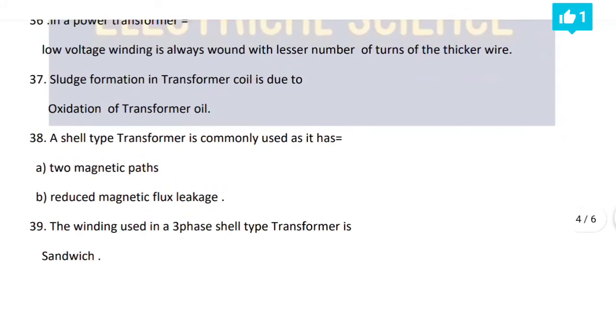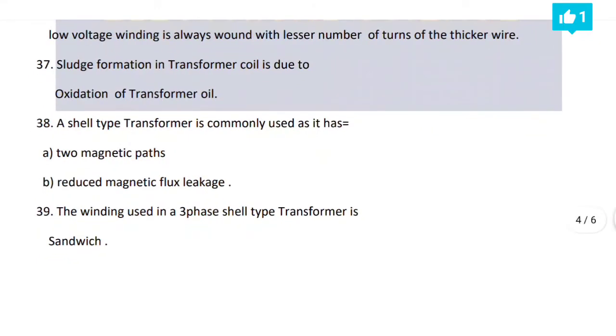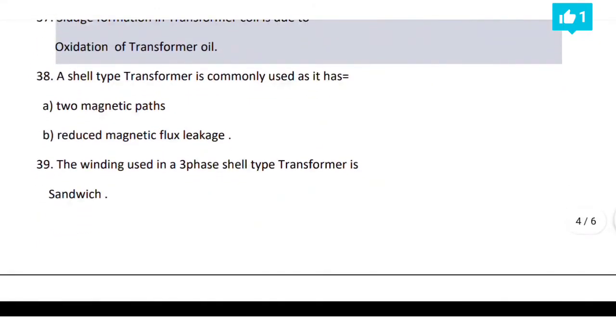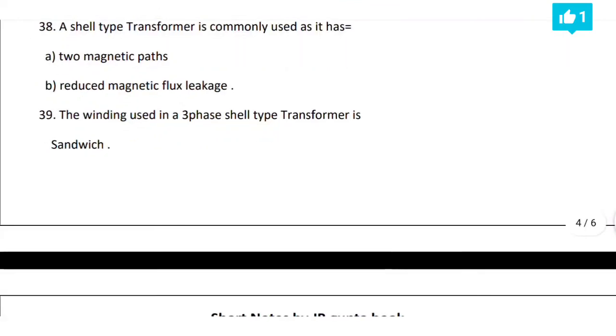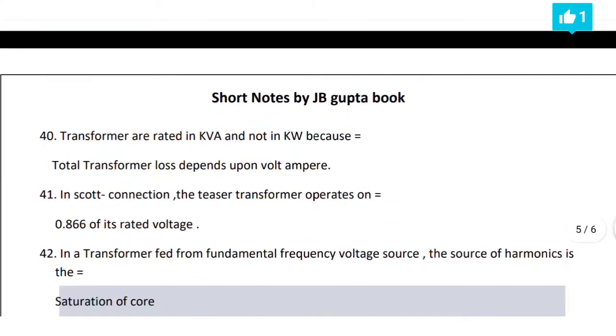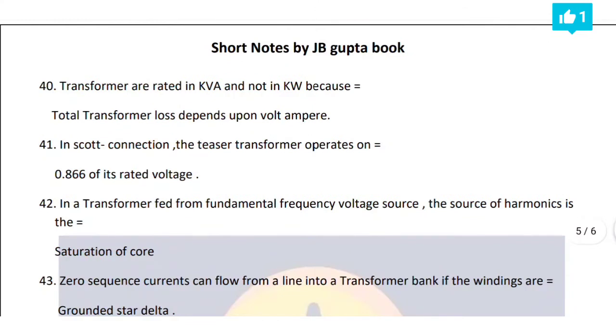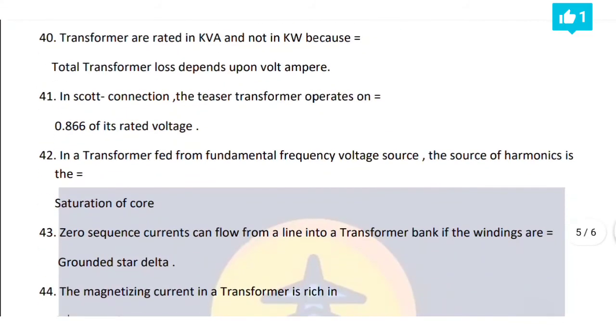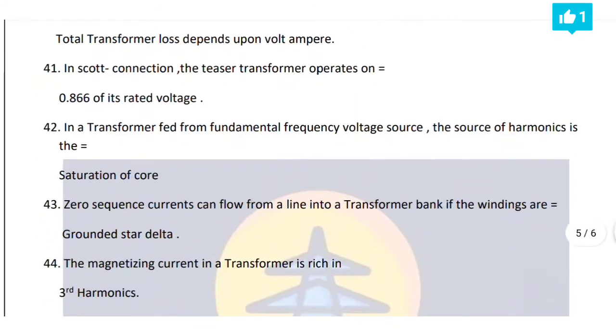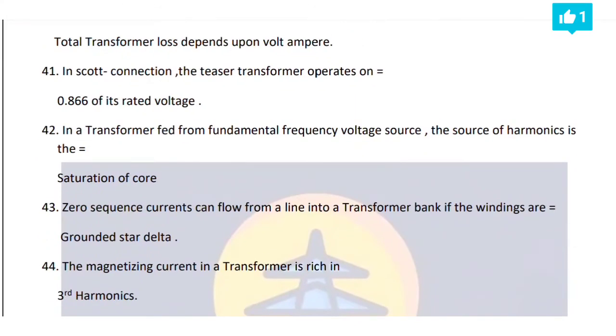38th point, a shell type transformer is commonly used as it has, first point, two magnetic paths, second point, reduced magnetic flux leakage. 39th point, the winding used in a three-phase shell type transformer is sandwich. 40th point, transformers are rated in kVA and not in kilowatt because total transformer loss depends upon volt ampere. 41st point, in Scott connection, the teaser transformer operates on 0.866 of the rated voltage.